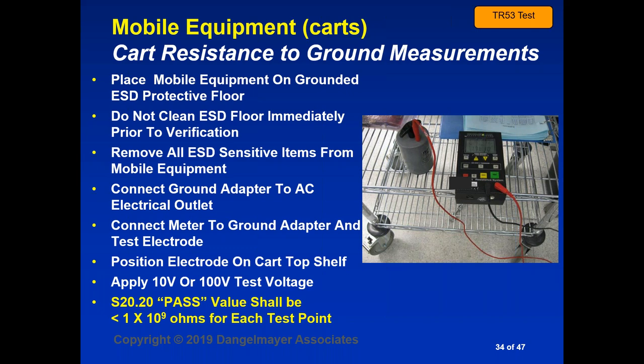Now, a few cautions about the cart. First measurement you make on the top shelf, second measurement you make on the next shelf, third measurement you make on the next shelf. You do have to measure every shelf, because there's no guarantee they're all connected together. Metal carts have for years used an insulator between the posts of the cart and the shelves, and that doesn't give you a ground connection. So there are simple ways to deal with that, but they must be dealt with.